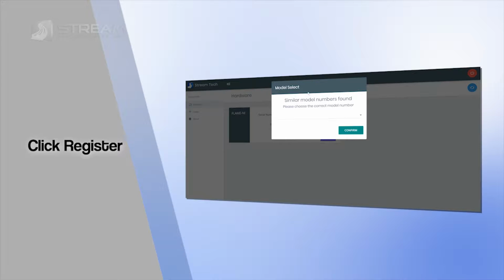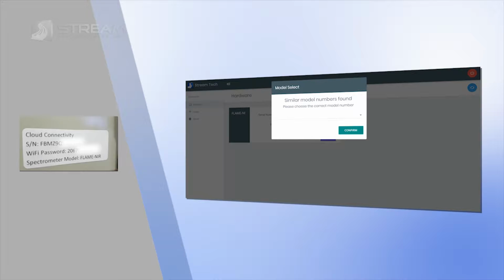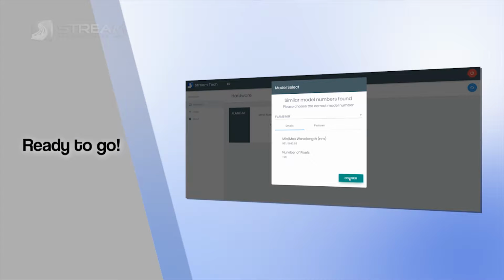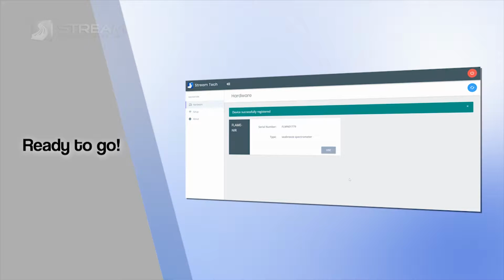And we get this model select screen that pops up. This means that there's similar model numbers that are in StreamTech's database of supported spectrometers that will show up. So we need to choose the correct model number that corresponds to our Flame NIR. And again, check the sticker on the front that tells you your spectrometer model to put into here. In our case, this is the Flame NIR. And just hit confirm. And now our device is registered and ready to use.